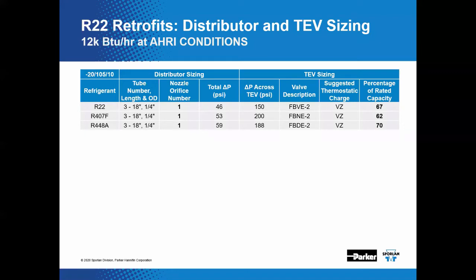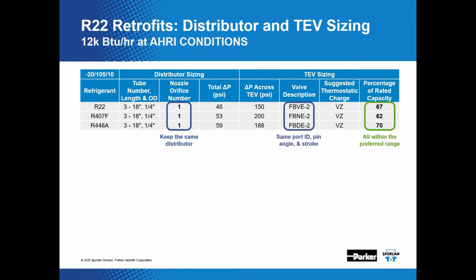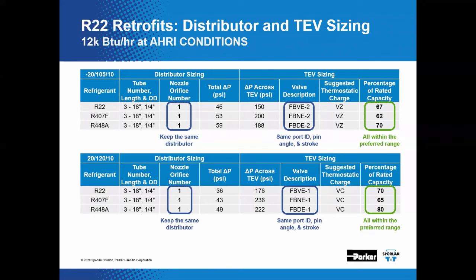Let's consider a retrofit of a similar 1-ton capacity system, but one that is R22. Again, we'll keep the same original nozzle selected as a number 1 nozzle for R22. We see that our total delta P goes up with 407F and 448A. We expect this because we know mass flow is somewhat higher. Note though, that still leaves us with more delta P available to drive flow through the thermostatic expansion valve. We keep the same internal diameter of the port, pin angle, and stroke for R407F and R448A. And we find that our percent loading really doesn't change too much in comparison with R22. For a medium temp R22 to R407F or R448 retrofit, the results are essentially the same.